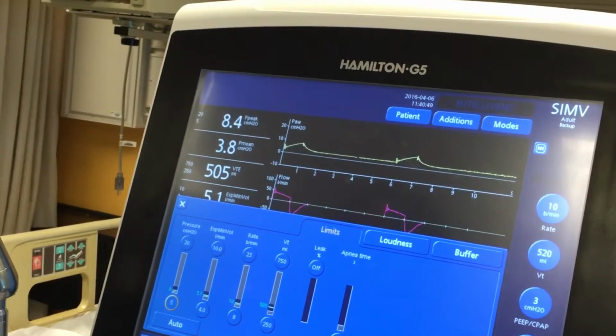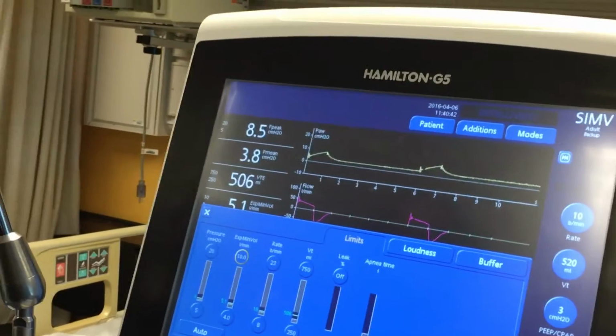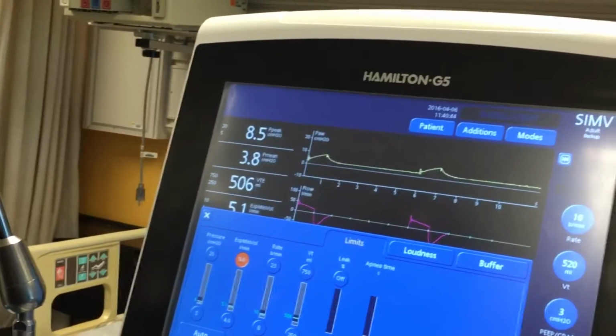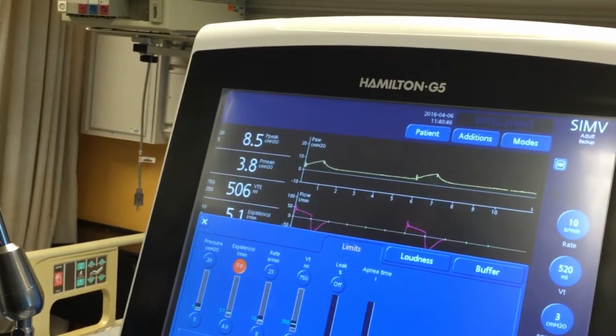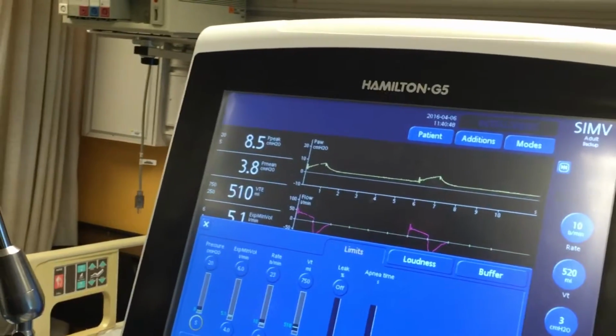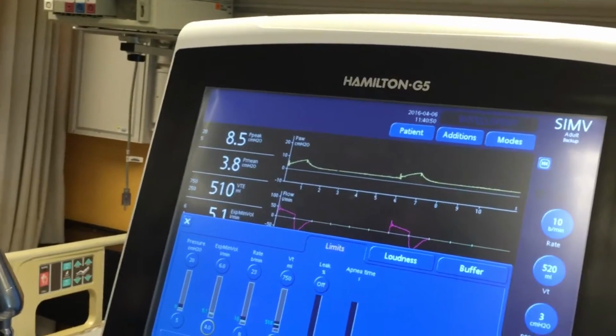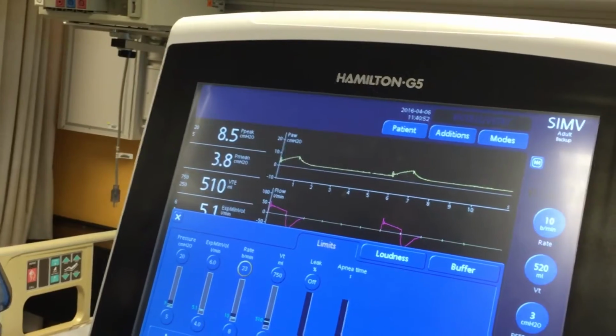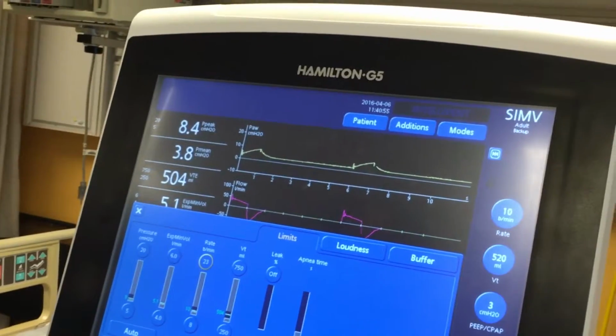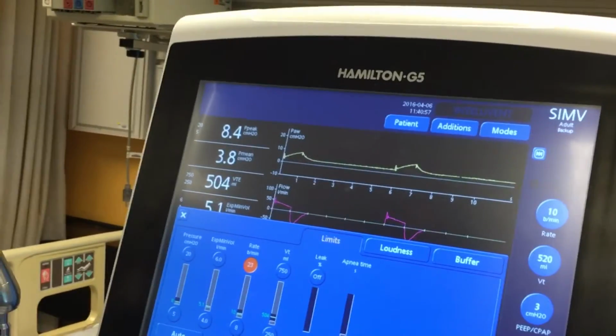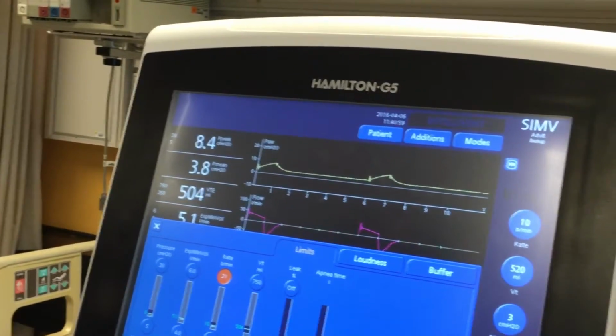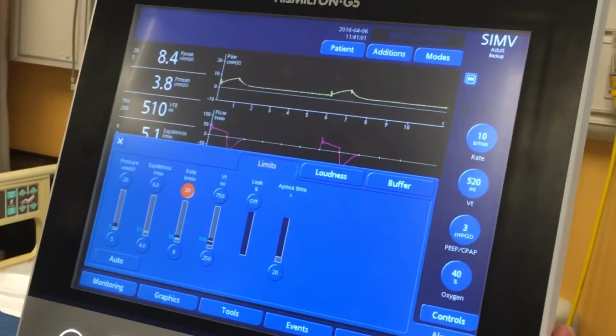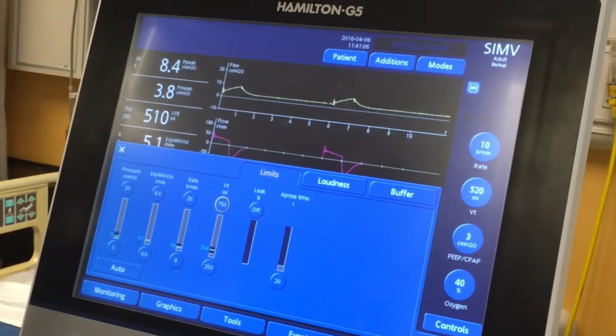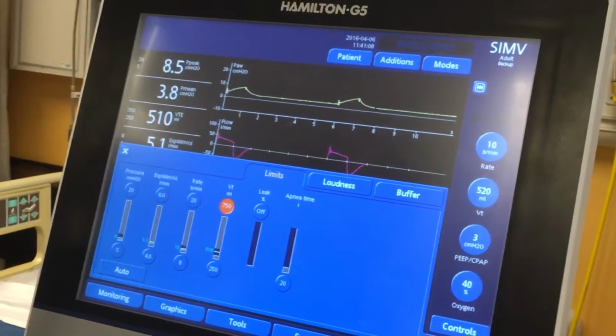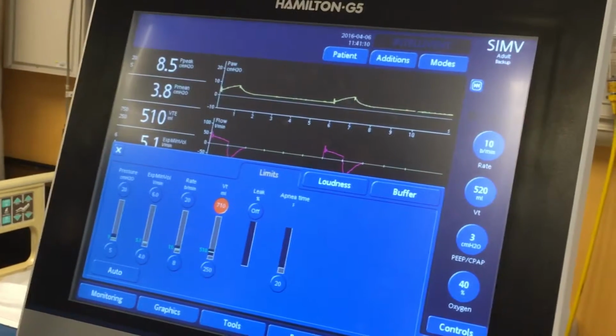And then next, it'll be fill in the blank. Blank to blank. Six and 4 is good. It's one above, one below minute volume. Your book doesn't talk about that, but other breath rate books usually say one up, one down. Since we have it at 10, we'll set it at 20 because it's 10 above, right? And then tidal volume, 620.